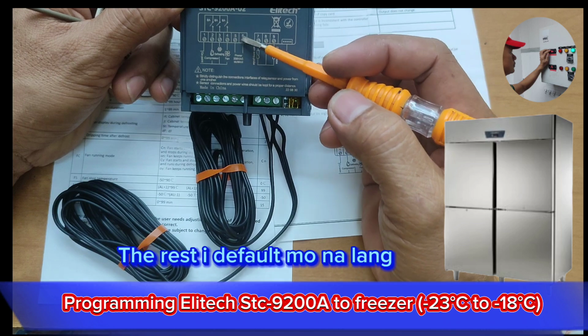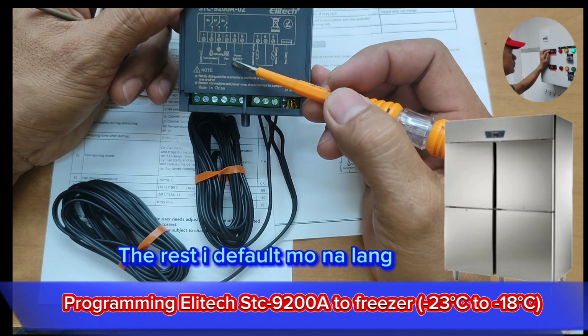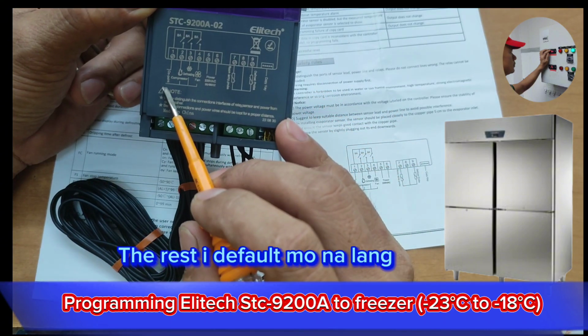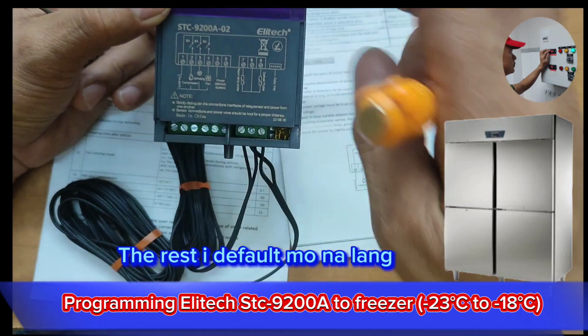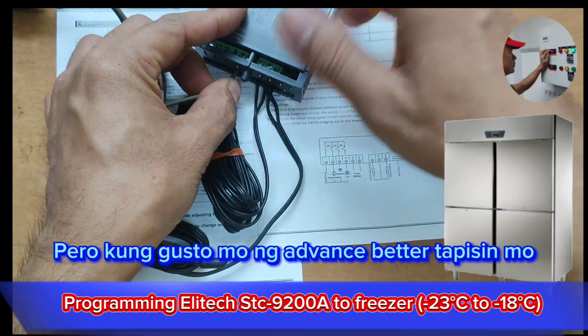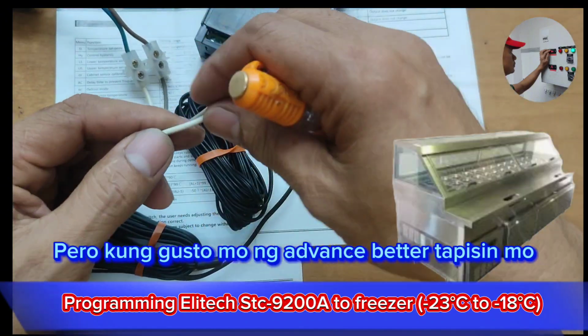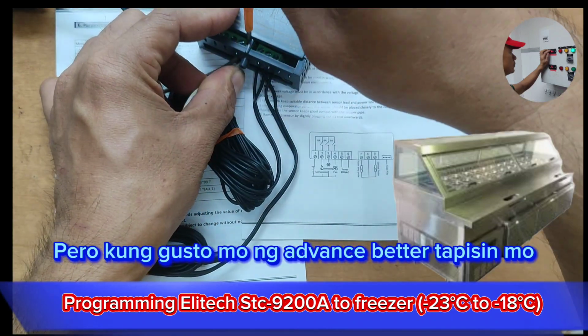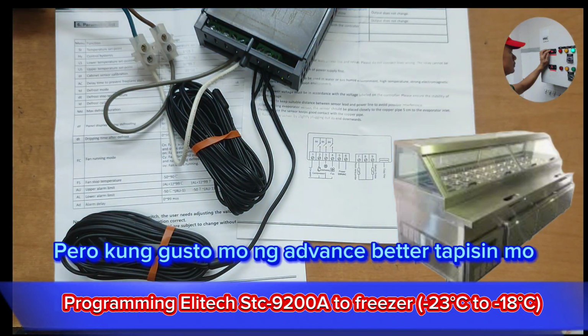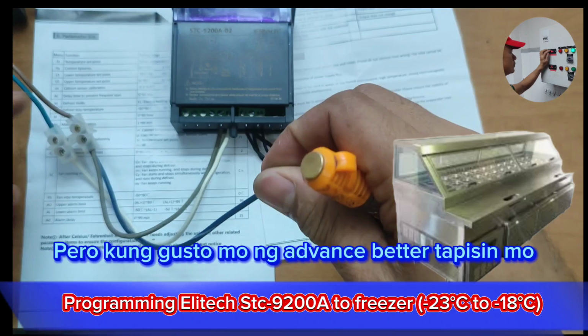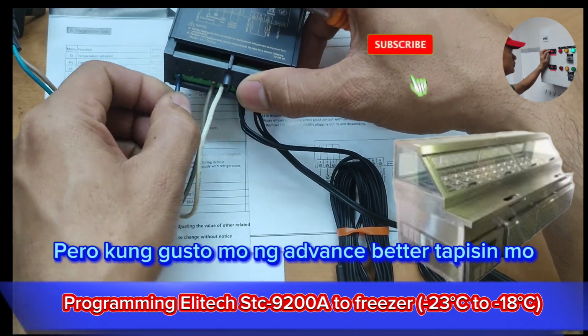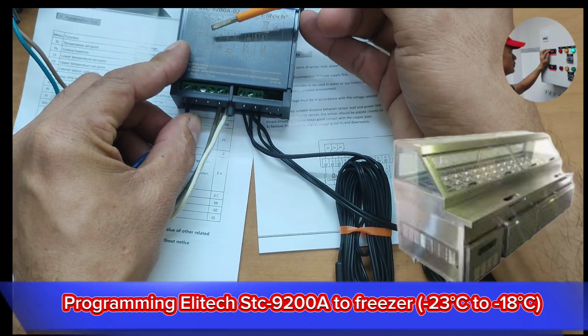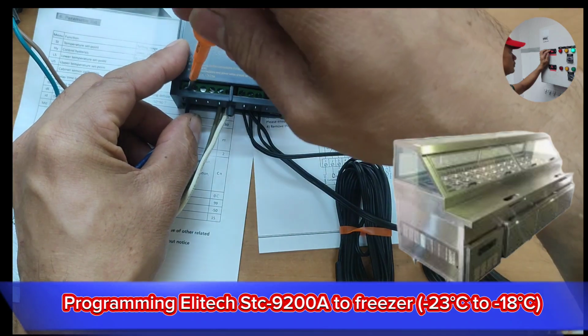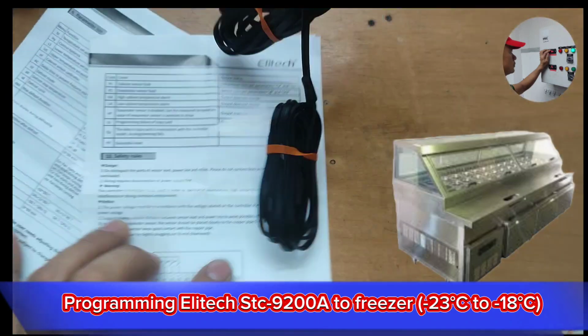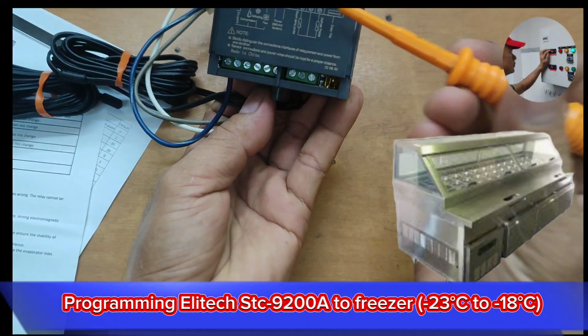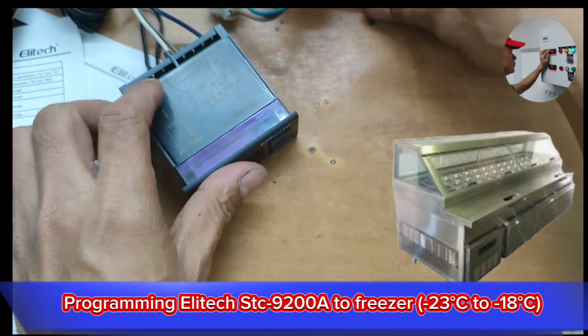If you wire this control, wire it to 5 and 6, your 5 will be your line, and you need also to wire the 1, so you have two lines here, 5 and 1. But right now I'm not going to wire that because our intention here is only to program it. Here I also supply terminal number 1 as my hot wire or live wire, so we can activate the compressor, defrost, and the evaporator fan. We're going to plug this here, 5, 6, 5, 6, okay, and power this on.